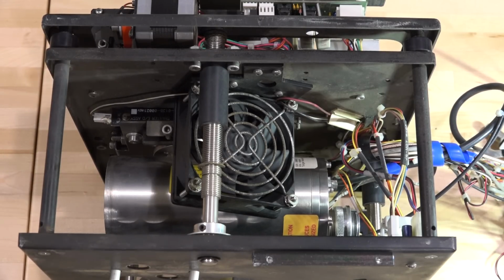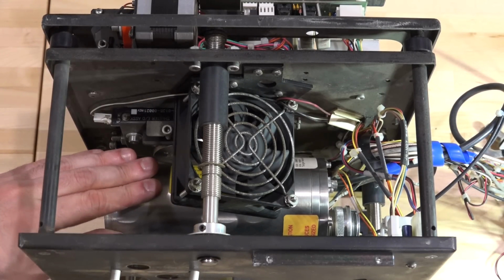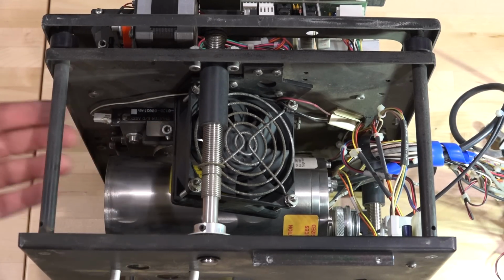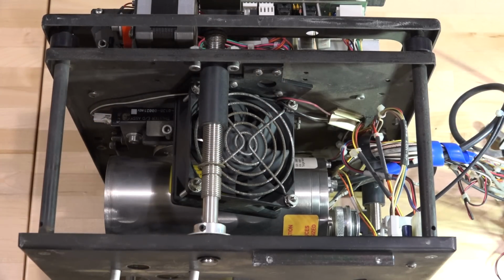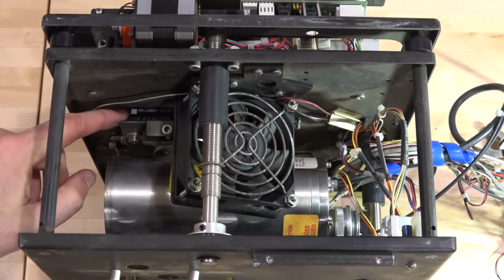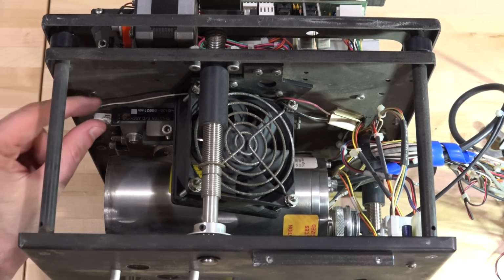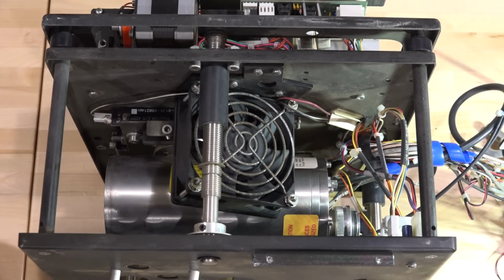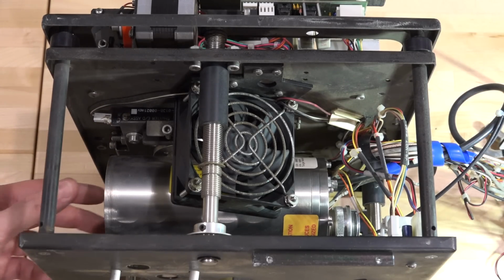And another 90-degree turn, and here's the fan blowing onto the X-ray tube. Nothing surprising, but this must have been running for a long time in a fairly humid area because there's some rust on this, and it's just dust everywhere. They must have never turned this machine off. And you can see the other side of that shutter with a control over here which controls the shutter. There's a part number on it. It might be worthwhile to dig it out, see if we can get some more information about it.